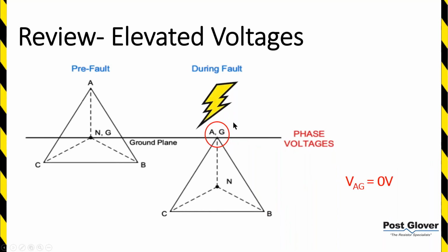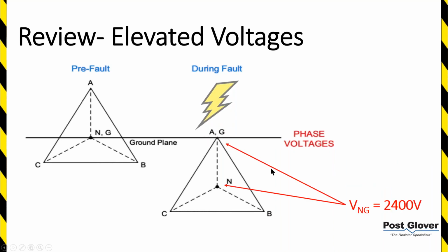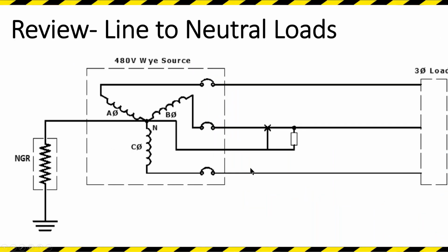Of course, since your A phase is grounded, you're going to be at 0 there. And the neutral is no longer tied to ground directly, so we're going to have more of a line-neutral type value here. So let's move on. Let's talk about line and neutral loads.